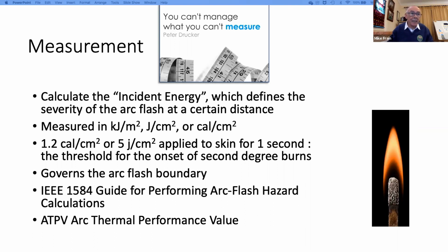So the last one, I'll try and explain it very quickly for today, but arc thermal performance value refers to PPE. It's a measurement of a fabric's or PPE. It might be a fabric, it might be other clothing like gloves or whatever. It's the ability to protect an individual from a burn due to exposure to an incident energy level resulting from an arc flash. Basically, it means that the incident energy will be attenuated to 1.2 calories per square centimetre, or the onset of a second-degree burn.